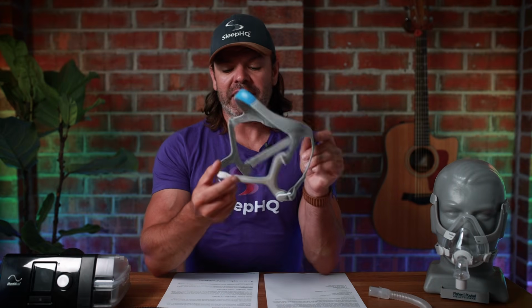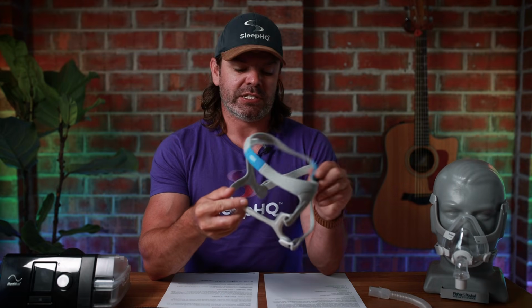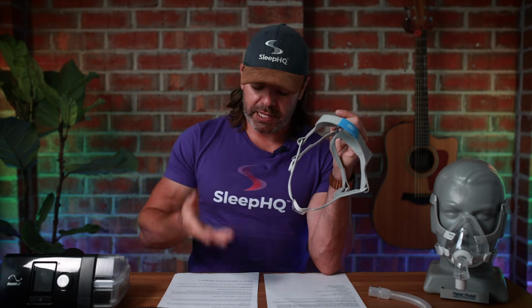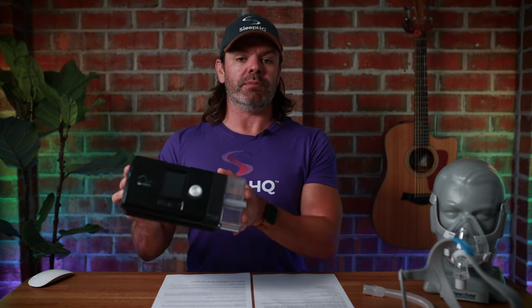Then you have the headgear and the mask frame. Once again, I'd say probably every 6 to 12 months. That's the recommendation here. And last of all, what is the replacement schedule on a CPAP machine? How long should they last? Well, ResMed states the product lifespan is around 5 years, but in my experience, if you're looking after them, using those hypoallergenic filters, stopping the dust from getting into the motor, you should get between 5 to 12 years use.